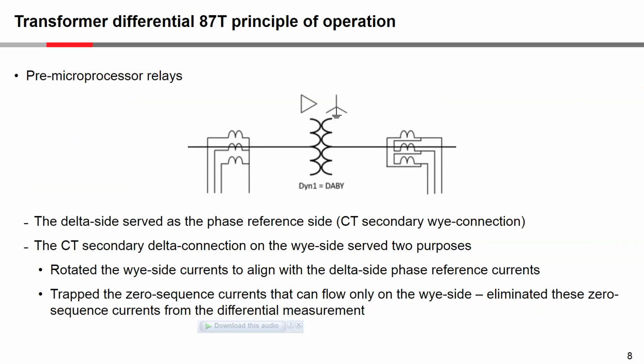All right, so what can we say then about these pre-microprocessor relays is firstly that the delta side served as the phase reference for delta Y transformers, because the CT secondary had Y connection. The CT secondary delta connection on the Y side served 2 purposes, and I've already mentioned what they are. Firstly, they rotated the Y side currents to align with the delta side phase reference currents, and they also trapped the 0 sequence. Okay, so what they did, they eliminated the Y side 0 sequence currents from the differential measurement, because 0 sequence currents are not flowing on the winding 1 or the delta side, and so you want to eliminate this 0 sequence mismatch in the calculated differential currents.